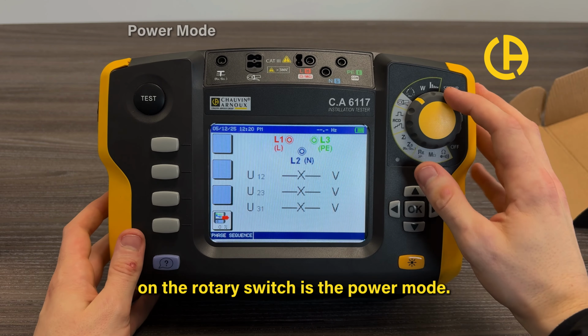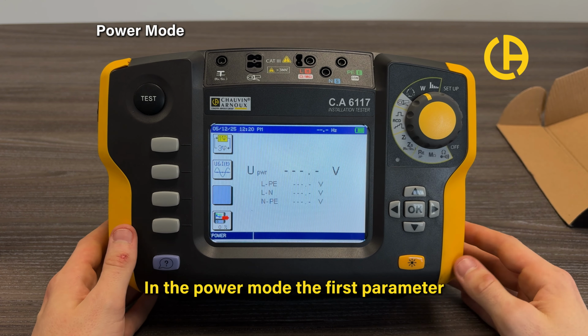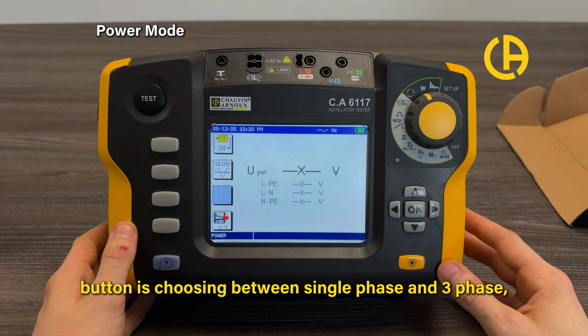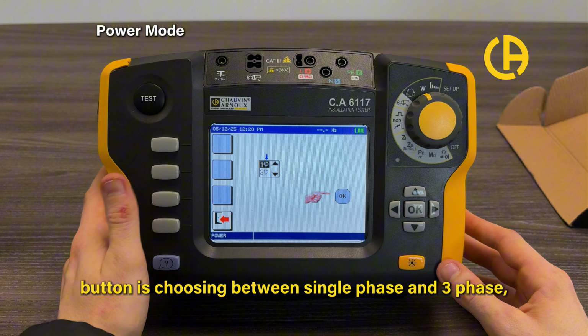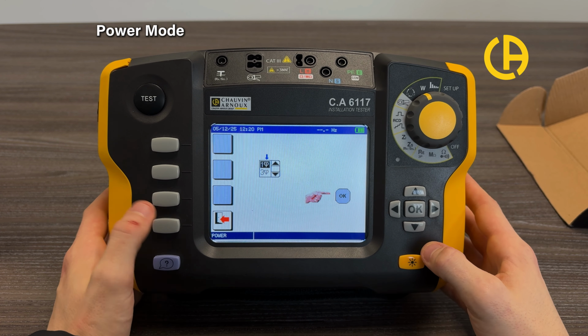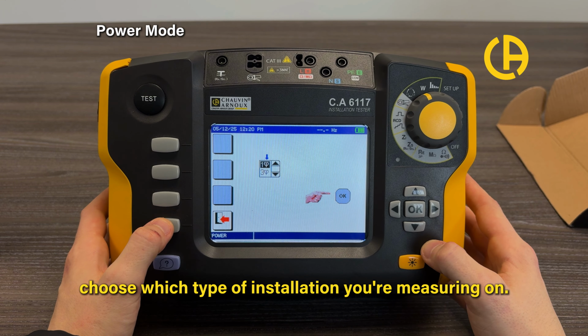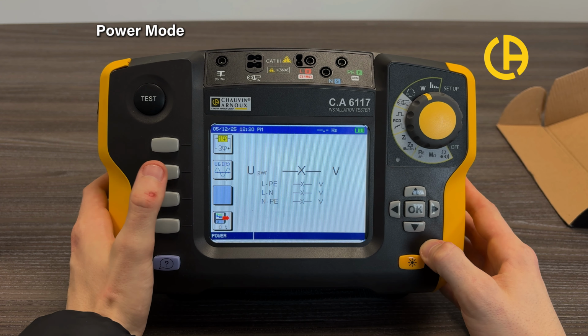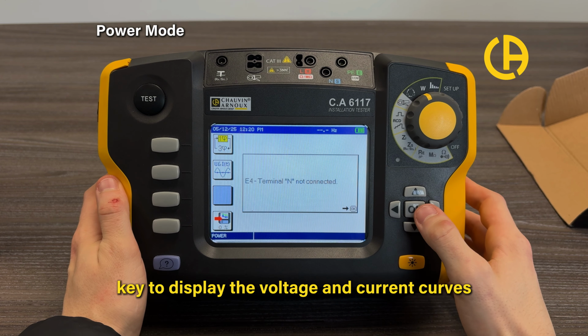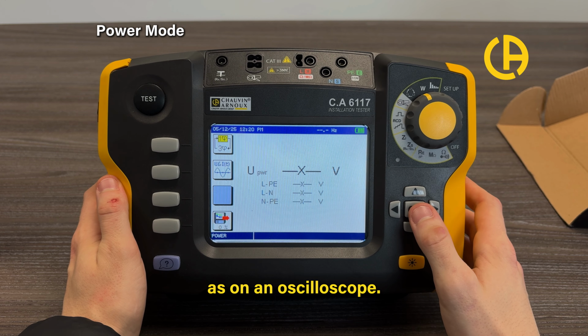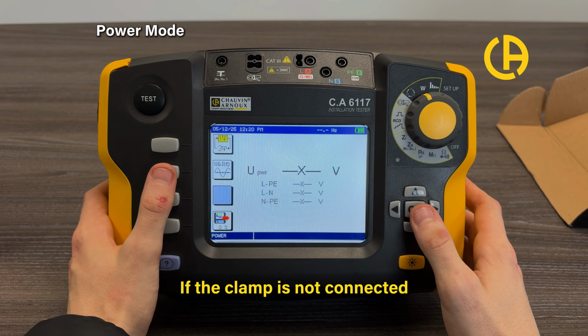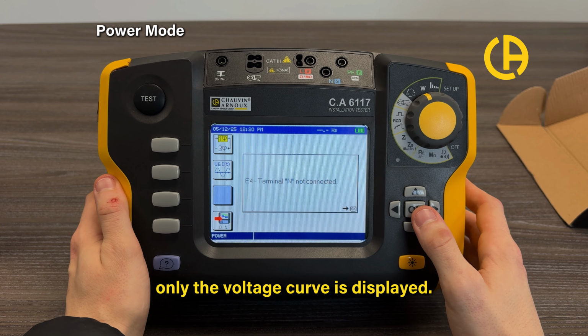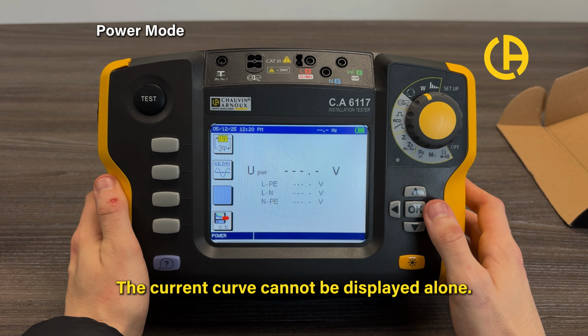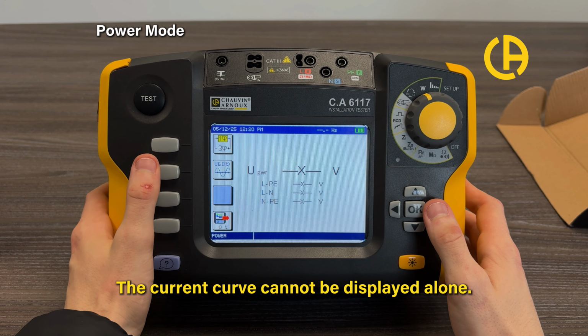The next function on the rotary switch is the power mode. In the power mode, the first parameter button is choosing between single phase and 3 phase. So choose which type of installation you're measuring on. Press the second parameter key to display the voltage and current curves, as on an oscilloscope. If the clamp is not connected, only the voltage curve is displayed. The current curve cannot be displayed alone.